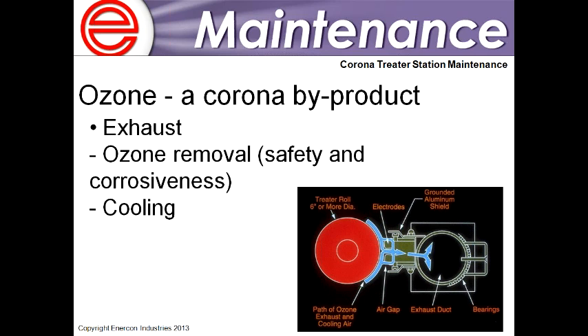First, we'll talk about ozone. The way that the treater design helps mitigate the ozone is, as you see in this picture, this shows our efficient design of how the electrode assembly draws in the air to cool the electrodes, but also how it captures and removes the ozone from the treatment area.